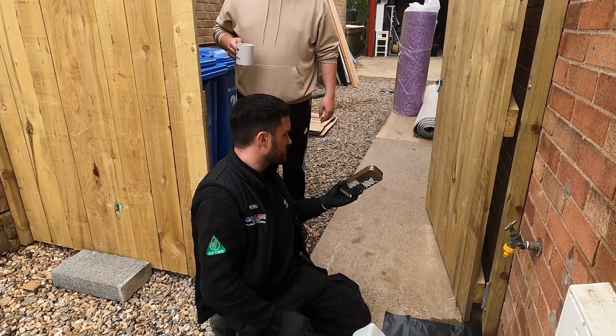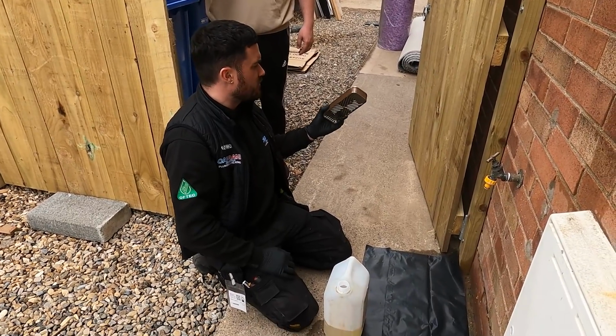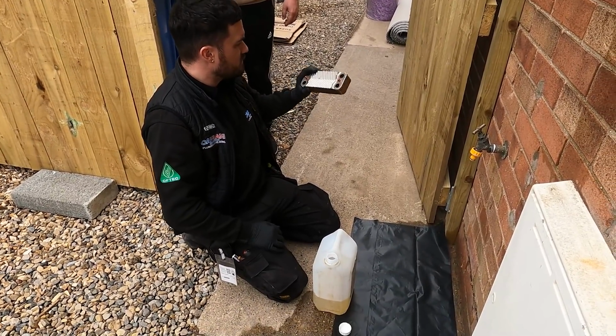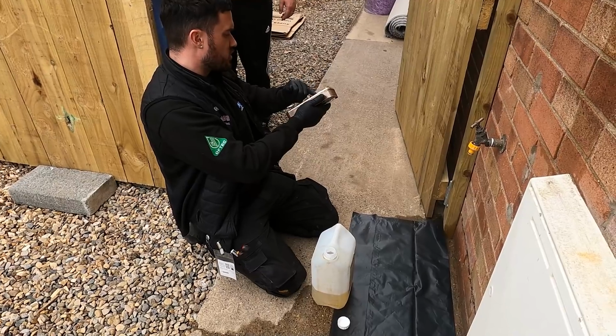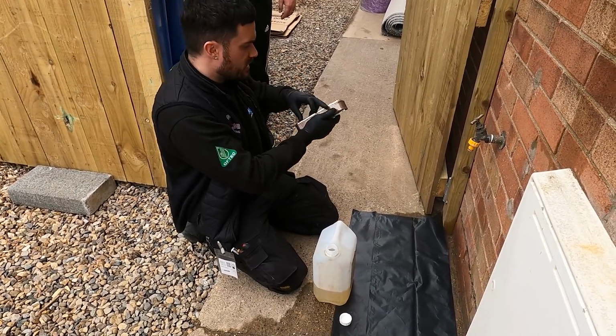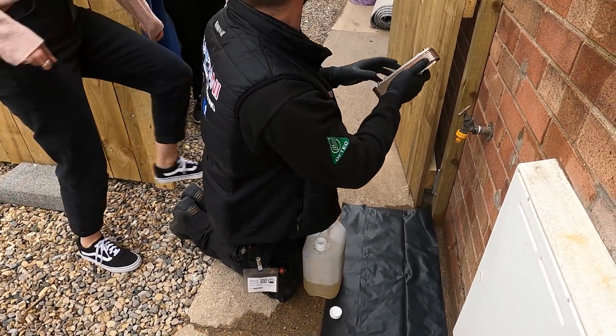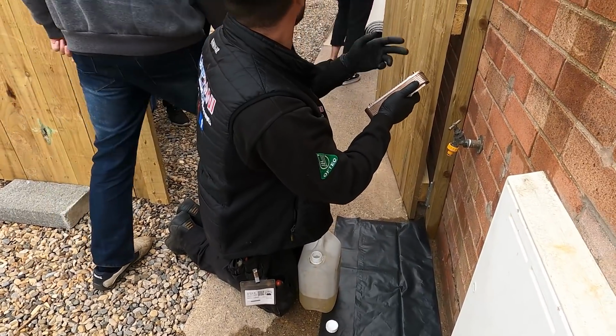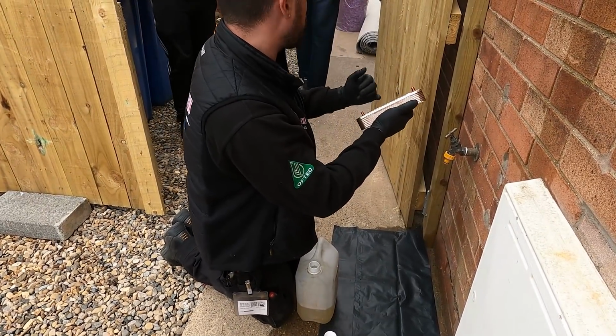It'll have been like that from the start, but it won't have been as bad. Because it's been stood empty, the particles inside will crust away. So when it initially kicks in again, the pump pushes it onto one corner, which it has there. Then when it's trying to run, the heat can't get out quick enough, so the boiler overheats.